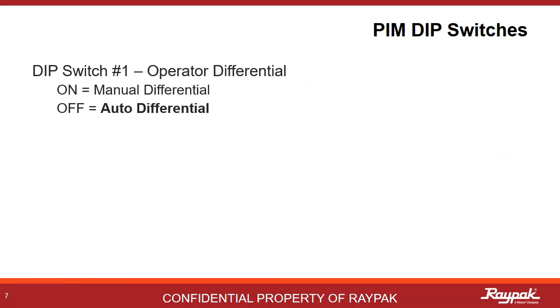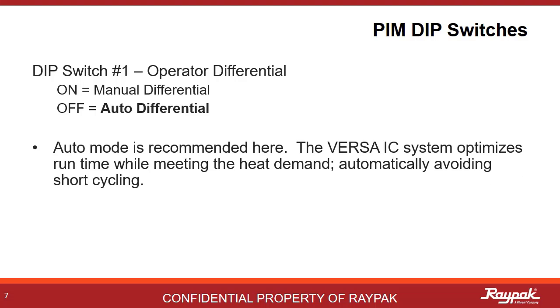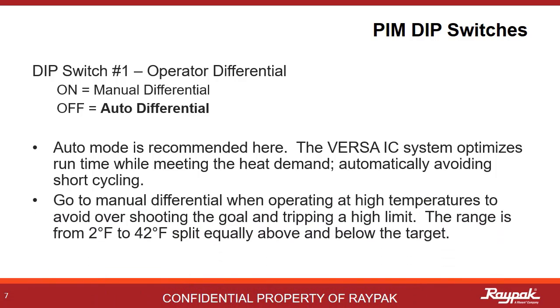PIM dip switch number one gives the operator the option of defining the temperature differential or to allow the Versa program to determine the best differential for the system. Auto differential is always recommended here. The Versa program will optimize based upon the system inputs to the best differential temperature to avoid short cycling. When it is necessary to run at a very high temperature that threatens tripping the upper limit, you can use a manual differential setting ranging from two to 42 degrees Fahrenheit, split evenly above and below the target.